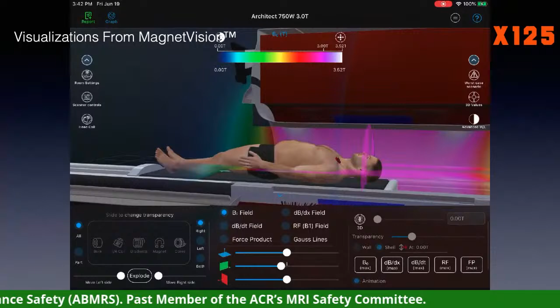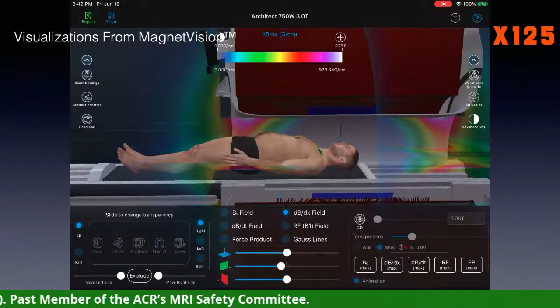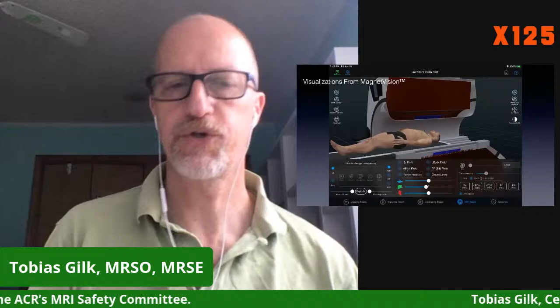It's really important to have an accurate understanding of the spatial distribution of the magnetic field, both static field and the product of the static field, the magnetic spatial gradient, because when it comes to reviewing MR conditional implants or devices, we really don't care what the patient is going to be exposed to. We only care what the implant or device that has an MR conditional threshold value is going to be exposed to. So that's static field, the B0, and the magnetic spatial gradient.